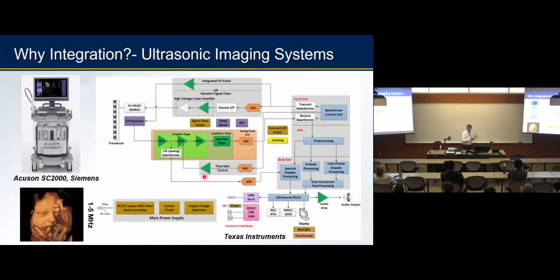Also, as I said, if you have all these elements in there, maybe hundreds of elements, then you have to connect them to a system, right? In a transducer, you have an array, but the ultrasound imaging system is pretty complex because you have to generate some high voltage pulses, and sometimes you need to time them so that you can send energy left and right, or you can focus it. Then you have to have a pretty low noise receiver because the signal that comes back is not very high. So you have to digitize it and do beamforming, all the calculations to get to your image.